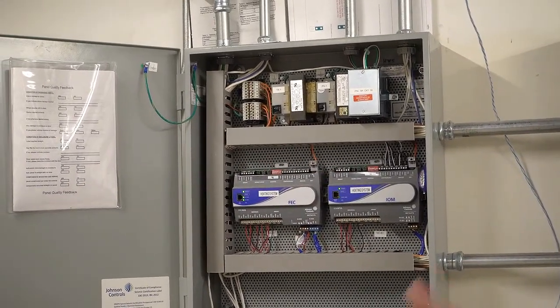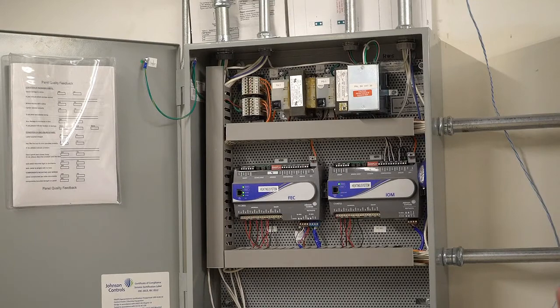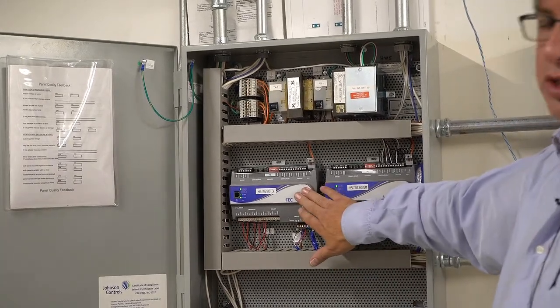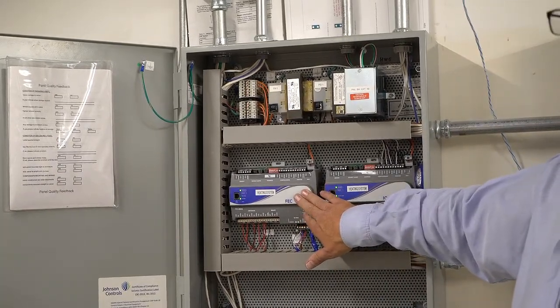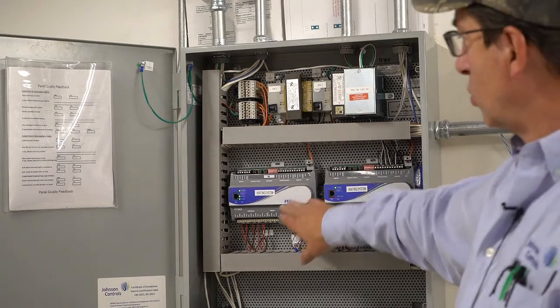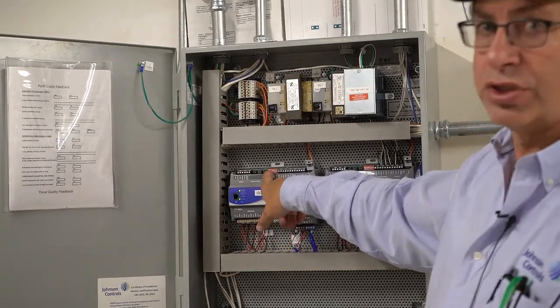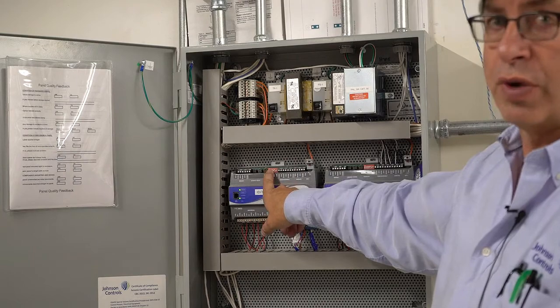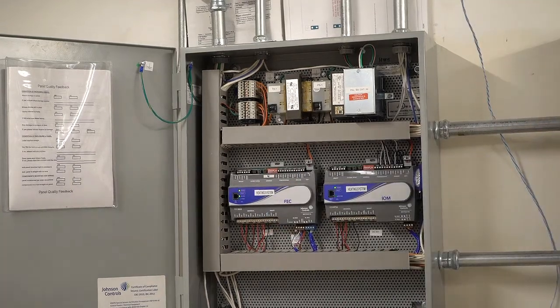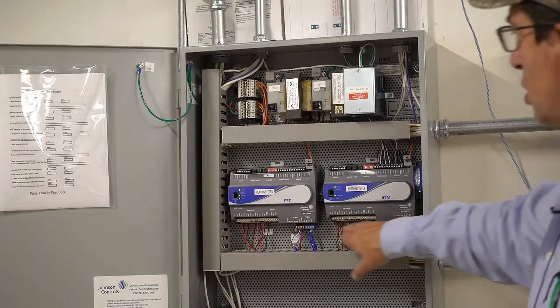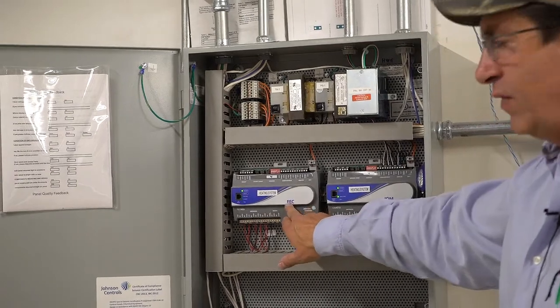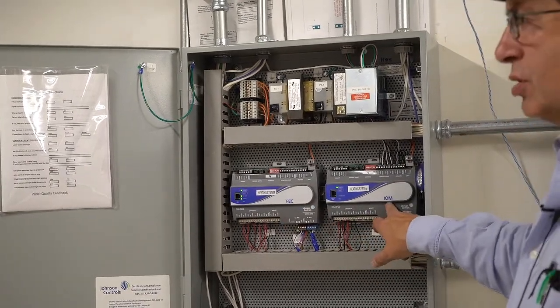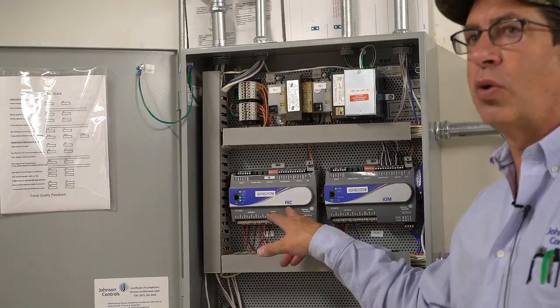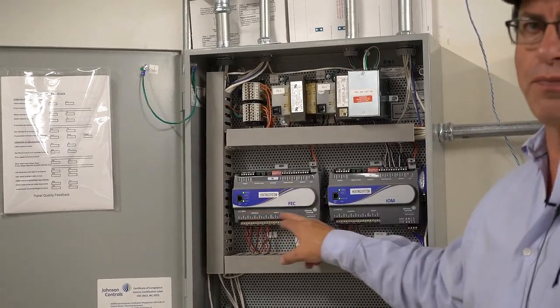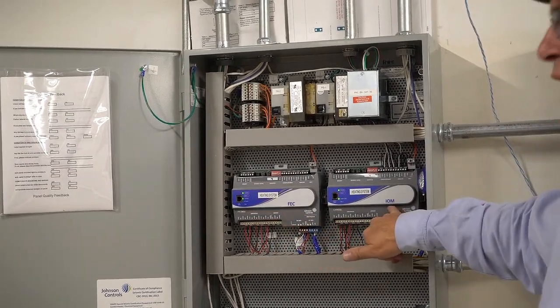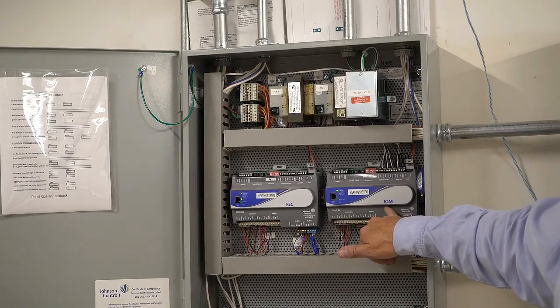We were talking about addressing the TECs earlier. We have the same thing with these controllers. These have to be addressed correctly or it'll take the trunk down. With these particular units, there's dip switches here where the white switches on the red background. That's how we address them. Something not to get confused is we have FECs and we have IOMs. FECs are field equipment controllers. These have logic in them. These are IOMs, input-output modules.